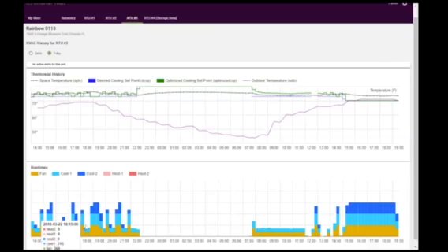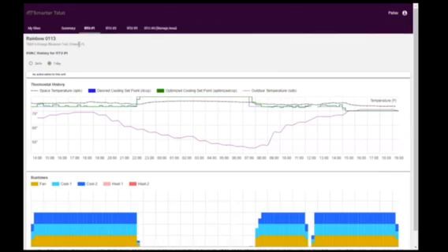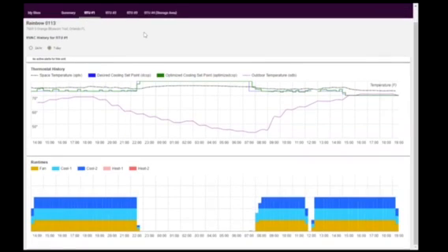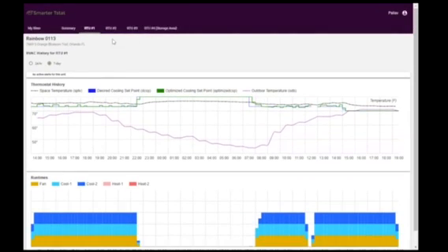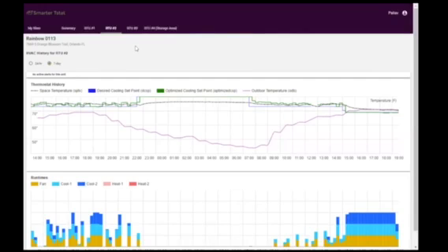5 minute period. And with each of these 5 minute steps, for example, on this side, down the corridor, RTU1 basically runs all the time because it's a very efficient unit, and it uses the cooling capacity from RTU1 to provide cooling for zones for RTU2 and 3, thereby ensuring that only the most efficient unit runs and also minimizing how many units turn on at any given time.